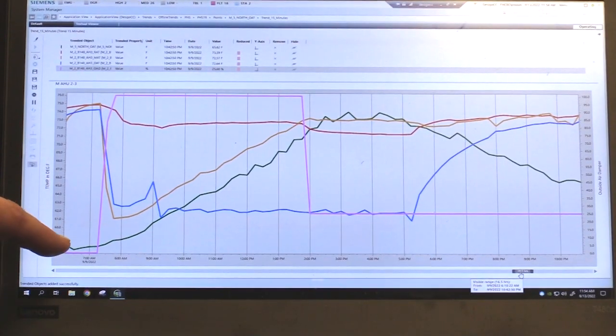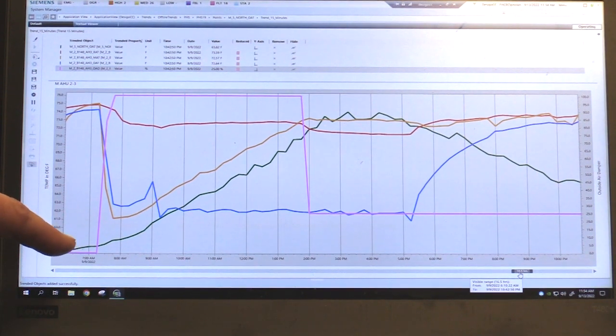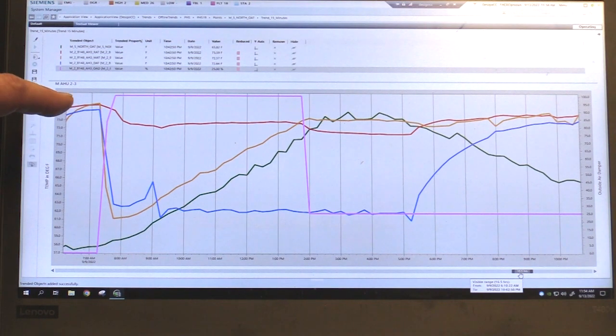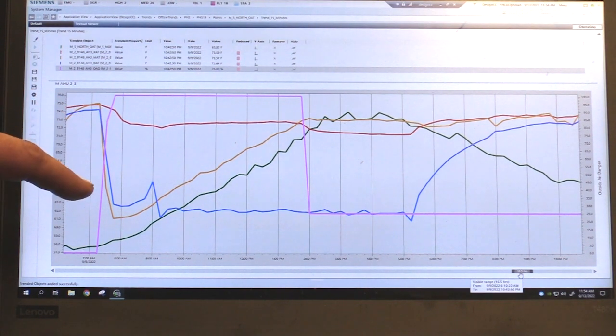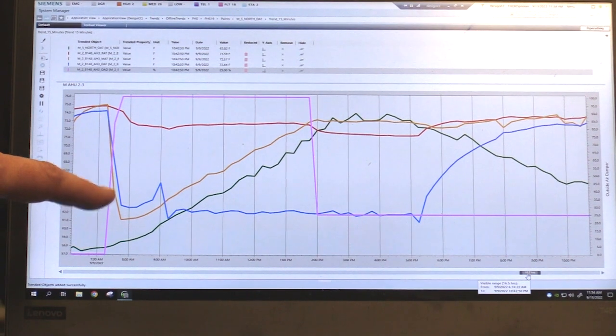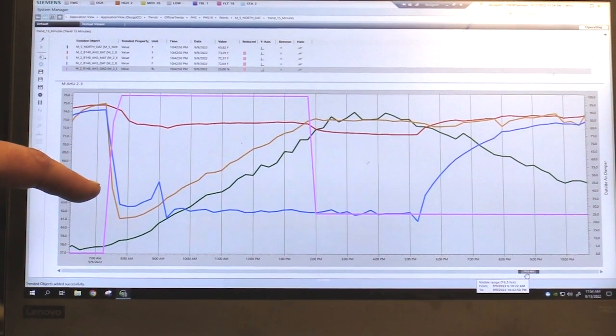So you'll see that the pink line is our outside air damper command. The green line is our outside air temperature. The red line is our return air temperature, the orange line is our mixed air temperature, and the blue line is our discharge air temperature.